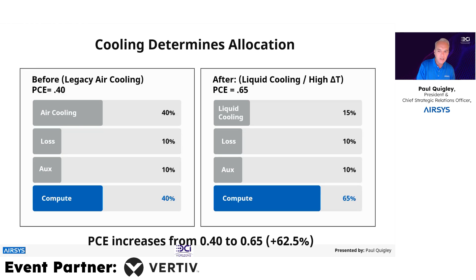What we're looking at is when we change the strategy and replace the existing air cooling with liquid cooling technologies at a higher delta T, and higher delta T is an important portion of this, we can drive PCEs. This is a very conservative example, but we can see a PCE of 0.65. That's over a 60% increase in PCE, or power that's provisioned to the facility that's now able to be provisioned to compute. That's significant, that's transitional change, that's potential there.